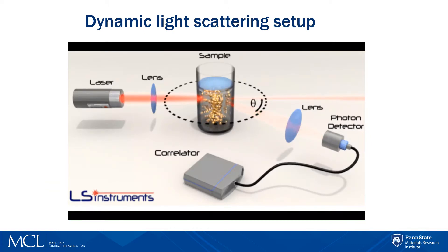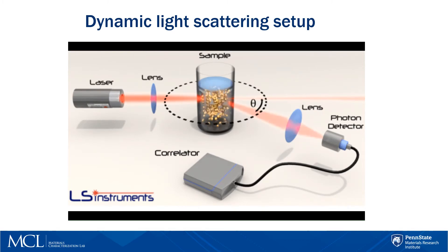The instrumental setup is simple. The sample is illuminated by a monochromatic laser beam. Particles scatter the light, and the interference of scattered waves generates a scattered light intensity signal. Since suspended particles undergo Brownian motion, this motion results in fluctuations of the scattered light intensity.